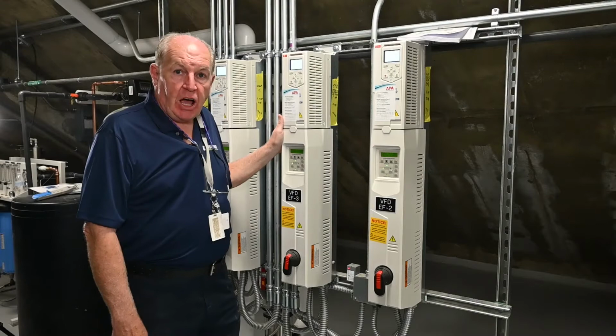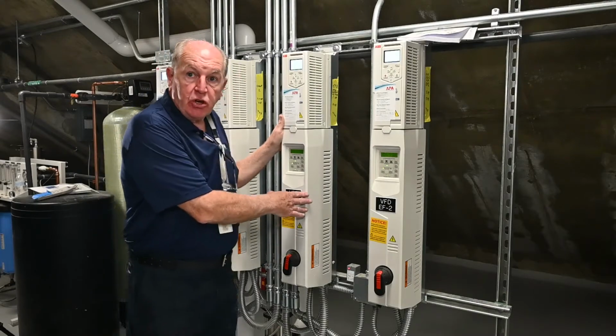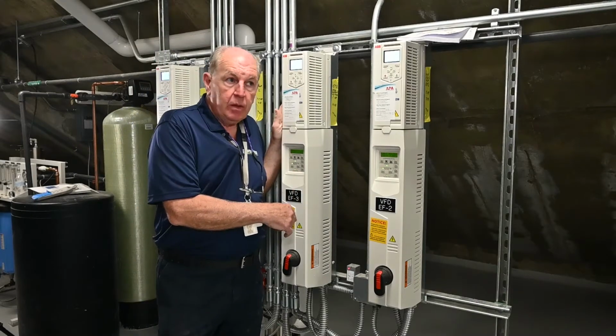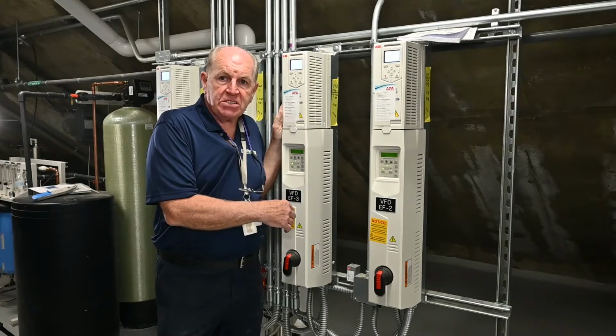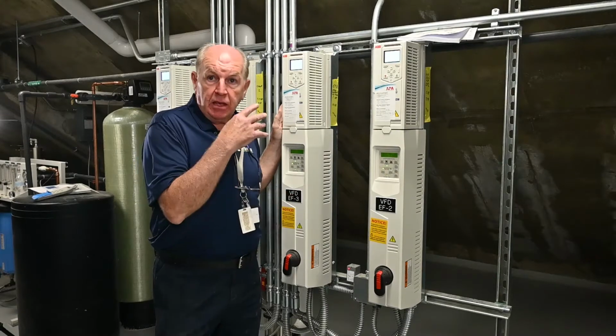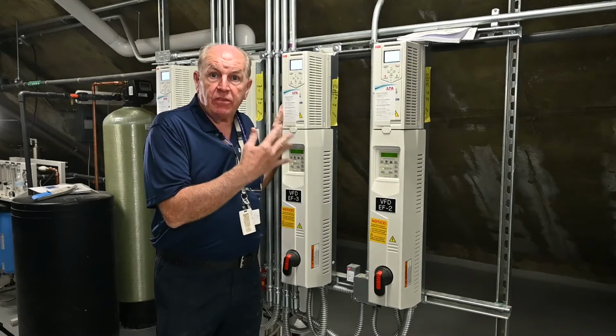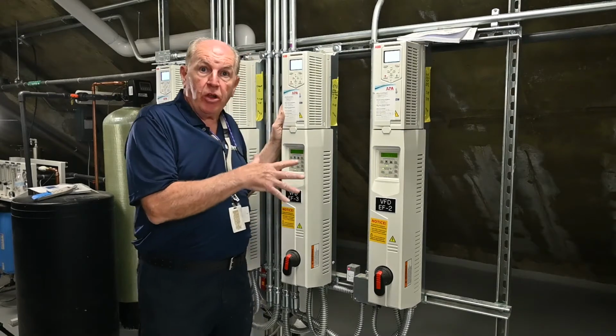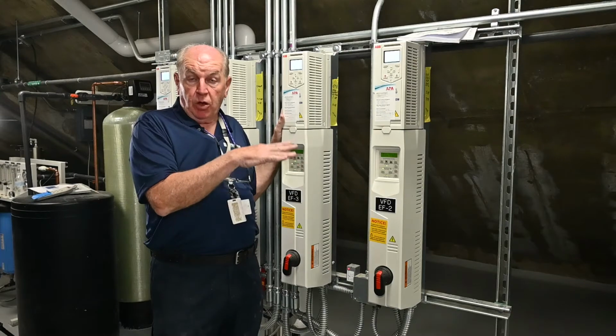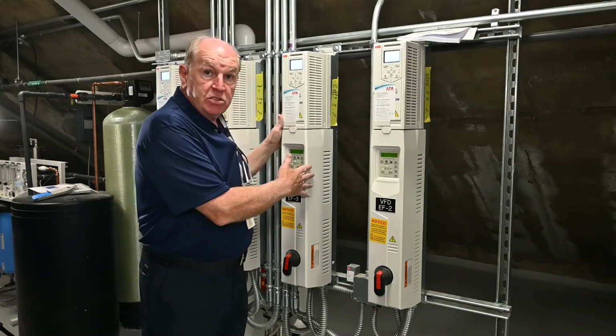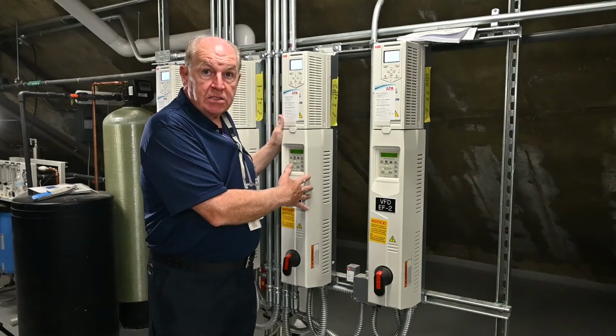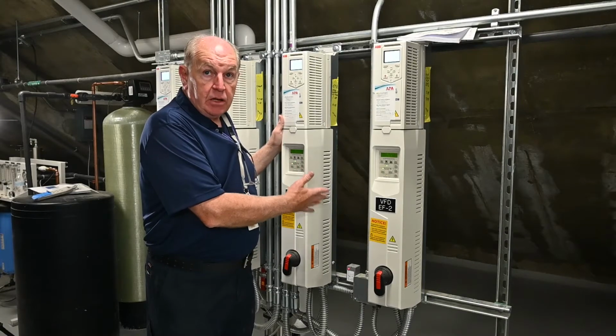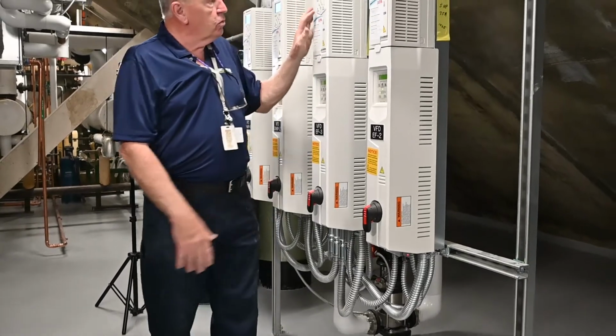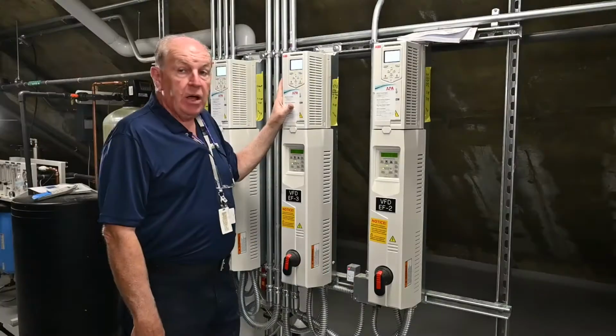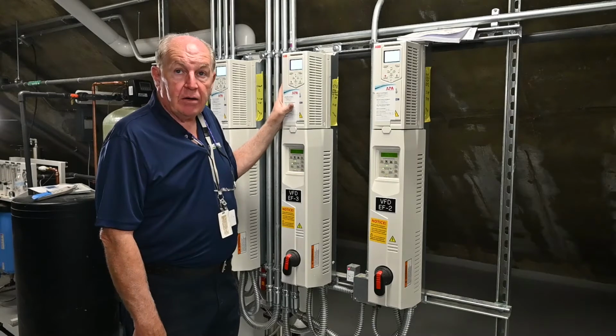There's 2 system exhaust fans. EF3 serves the conservation lab. On the 4th floor, there's a fume hood, and there's an EVAV, an exhaust VAV box. And there's also another one for the lab itself, not the fume hood. This fan serves both of those EVAVs. If either one of them has a call for exhaust or it's in the schedule, this will ramp up to the desired set point.